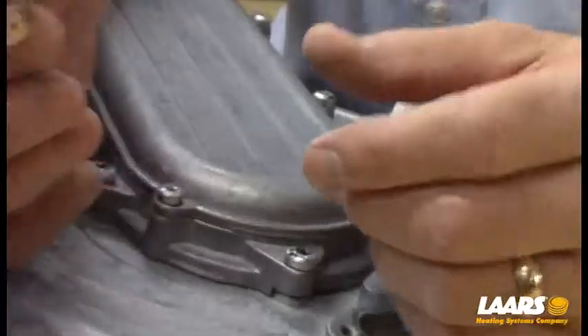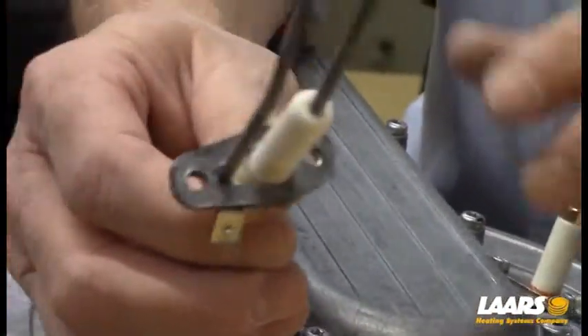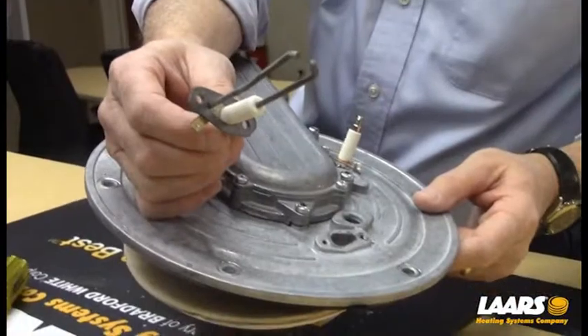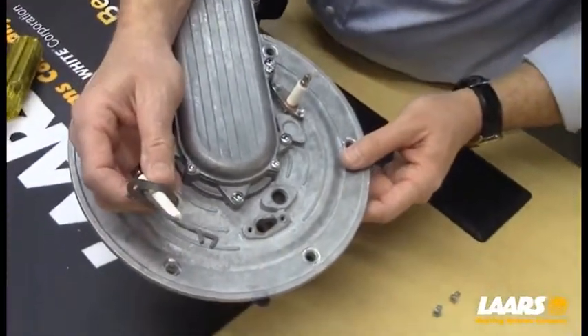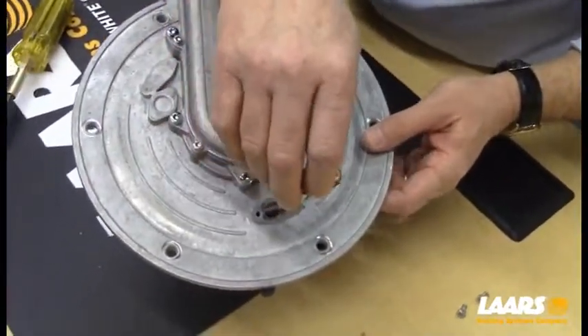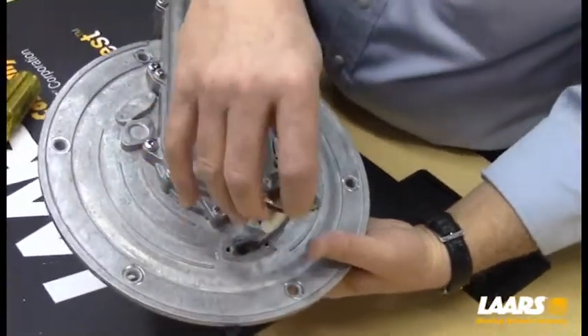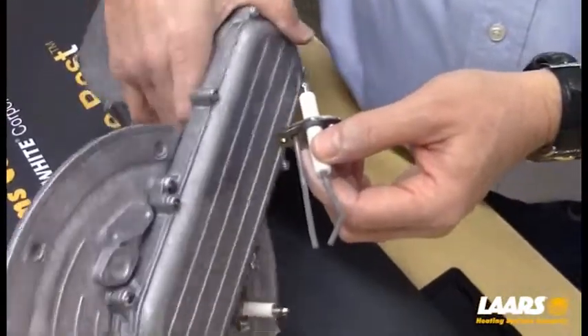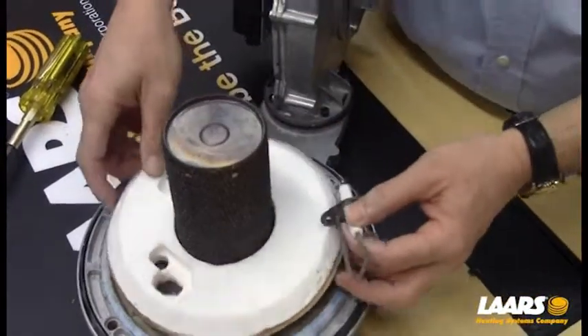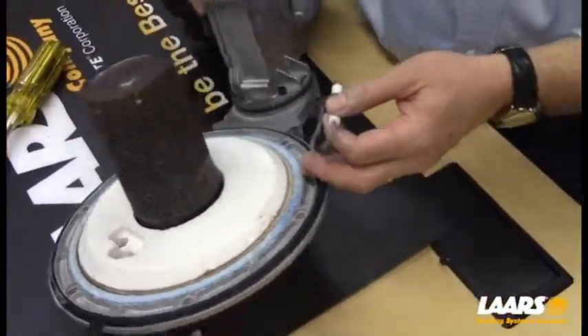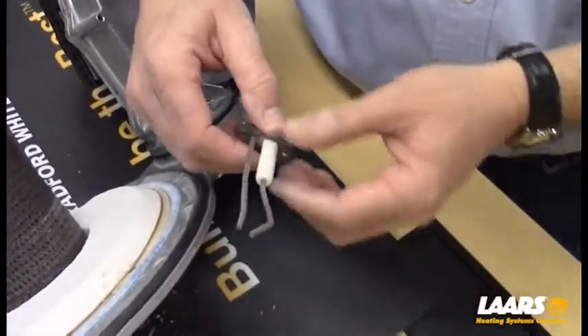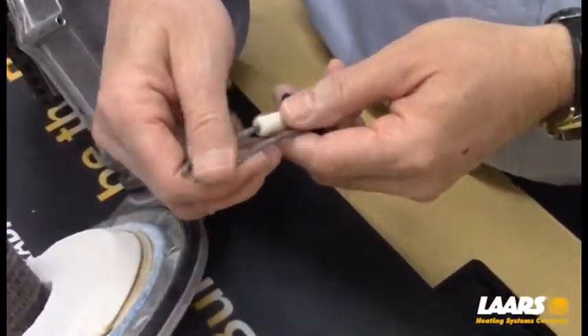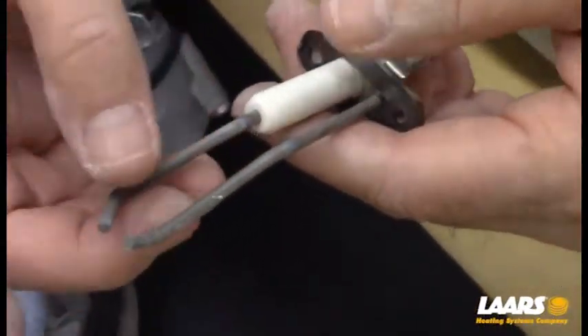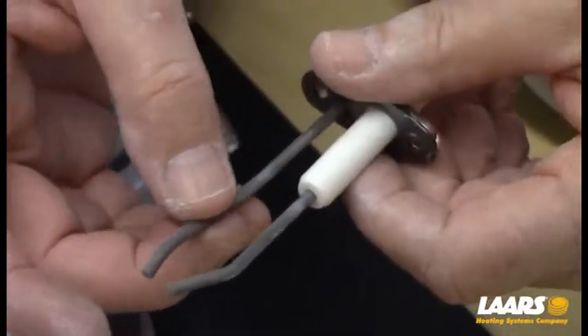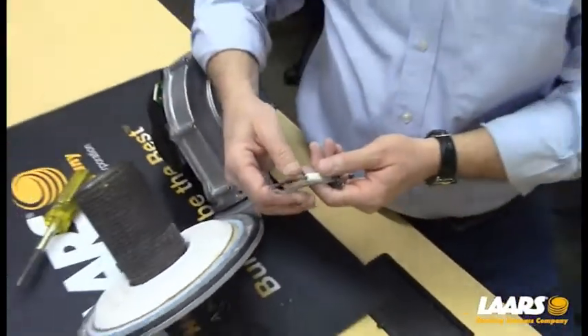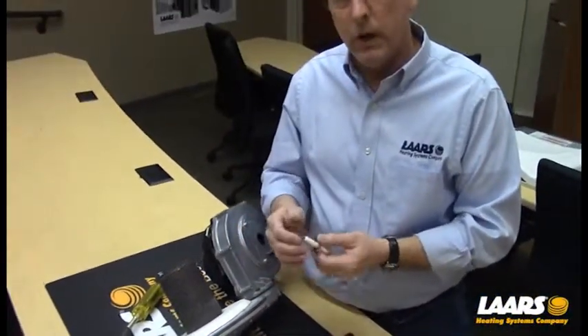If you need to replace it, you can order the igniter and flame rod with gasket, so they'll have new gaskets, and that's how you can replace it. Or if you wanted to just pull it with the burner plate in position, you could to check those. You can check this if you've got the burner head out of position. You could check the igniter and flame rod. If you need to clean them, please do not use an emery cloth or things to that nature. Just clean them up with a brush if you can. There is a thin coating on some of these igniters and flame rods, and you don't want to remove that thin coating. All right, so very simply, you can take this out, clean it up.